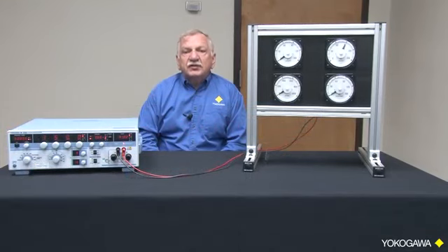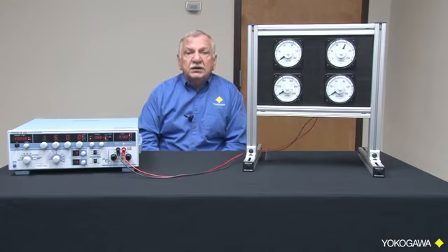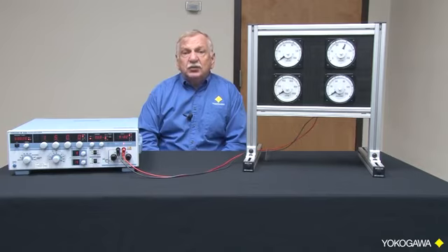For the last part of this test, we need to sweep the voltage from 0 to 150 volts. Typically, when testing these meters, manufacturers test up to 120% of the maximum range. This test is to check the meter for smooth pointer operation. To perform this test, the 2558A is designed with a built-in sweep function that allows you to sweep voltage or current from 0 to 120% of the maximum setting.